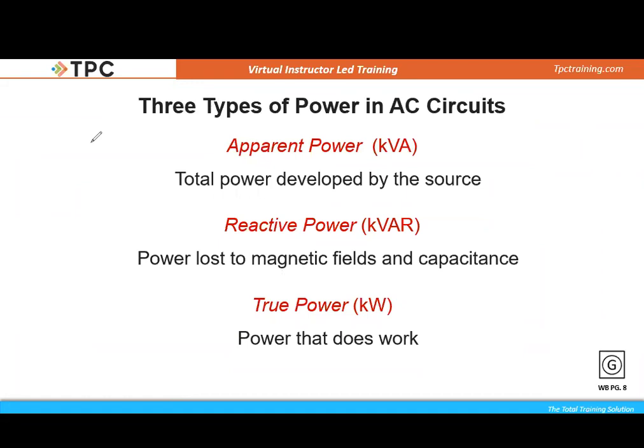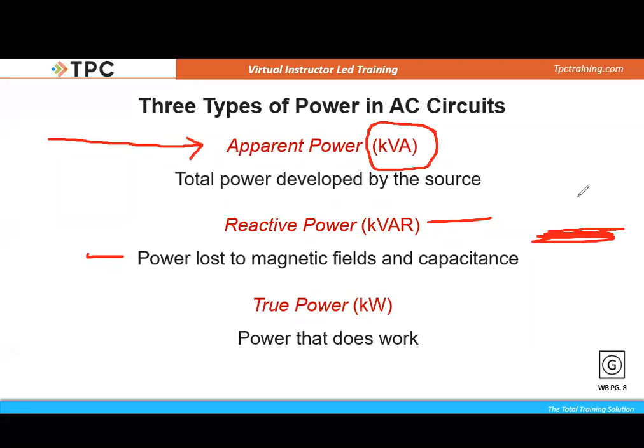How much power does that generator have to supply? Well, here it is. The generator has to supply what we call apparent power, or kVA. So that is going to include our reactive power. That's the power that we lose to energize our magnetic fields or charge our capacitors. That power just sort of goes back and forth in the line. And the utility is really not charging us for that power unless our power factor gets so out of line that they will charge us a penalty for that. And then we have our true power, which is the actual amount of power that's actually doing work.